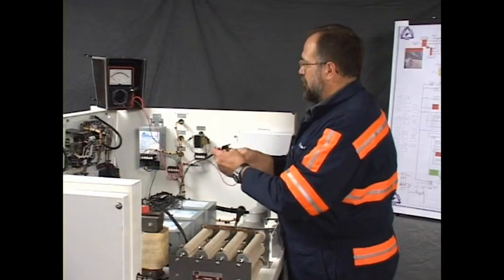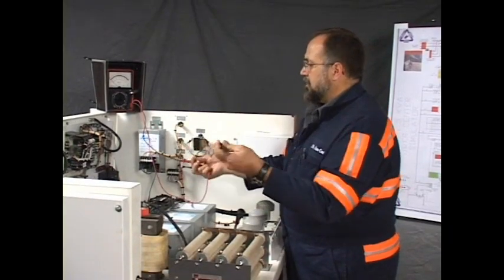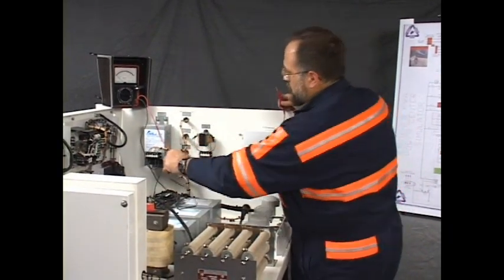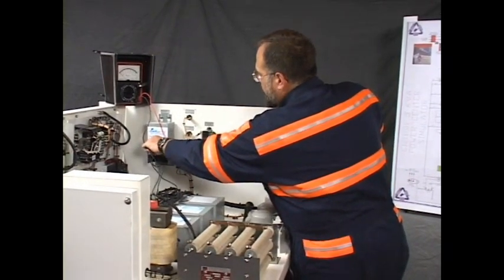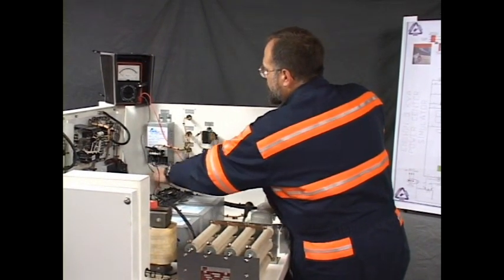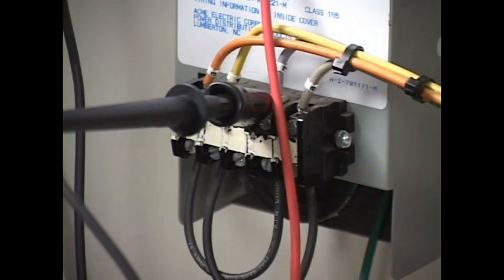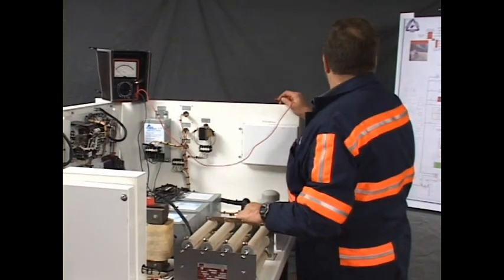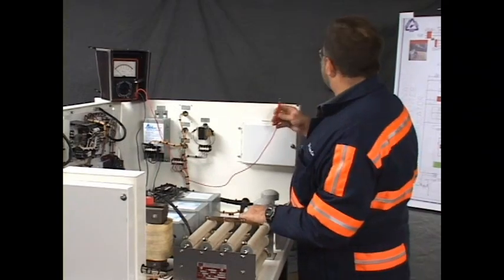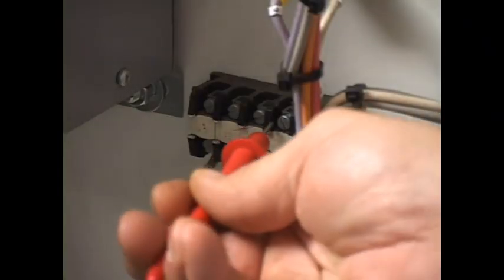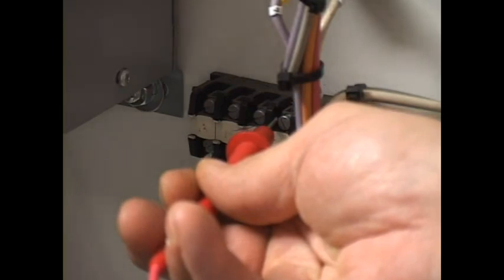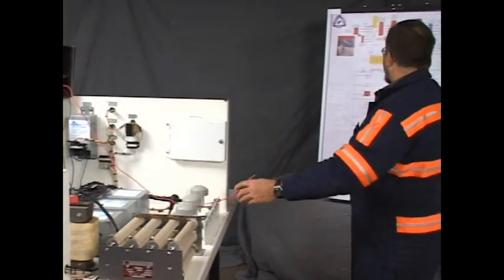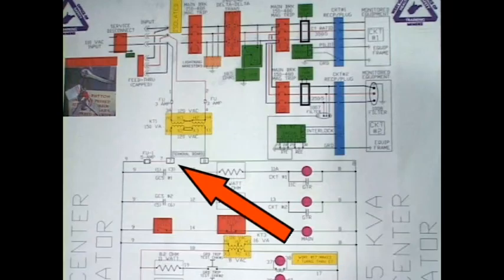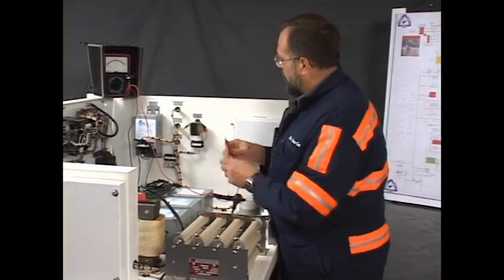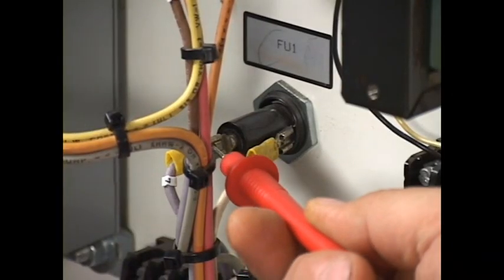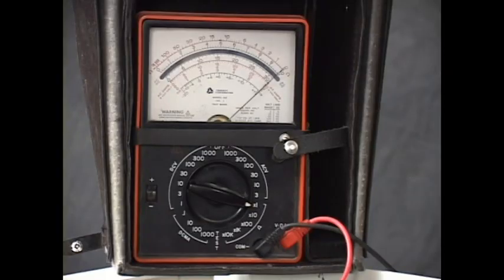As a beginning, we're going to start at the place where they said we had power. So I'm going to attach the black probe with the alligator clip to wire number 7. Begin there. Now, the first point I can check from there is the terminal block for wire 7, right here. That's shown on the print, right there. The next point, the line side of FU1, wire 7, and it's good.